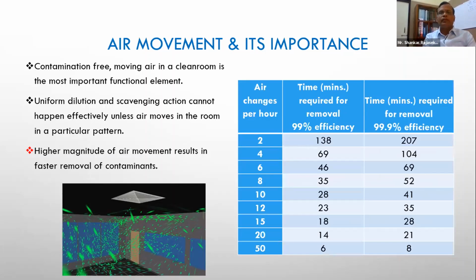So if you look at a table here, which shows that as we keep increasing the air changes per hour, the time required for removal to 99% efficiency keeps on falling down. And this is for achieving a removal of 99.9% efficiency. When we talk about air changes, it means we are recirculating the air with this many number of air changes through an adequate level of filtration and completely removing the particulate matter from it. So we do filtration at different levels, most typically a HEPA filter, which we will be talking about in the slides to come.